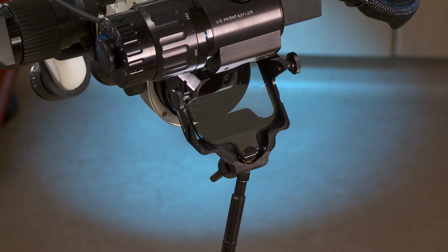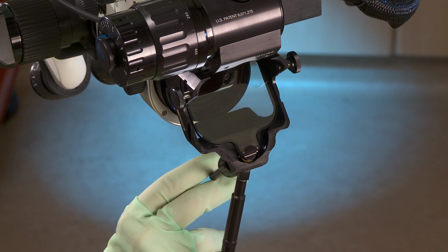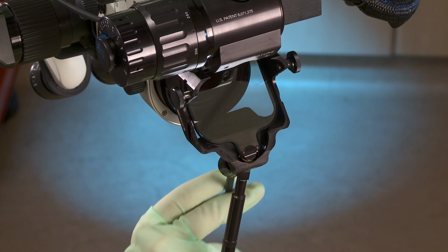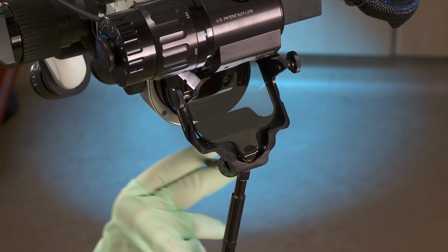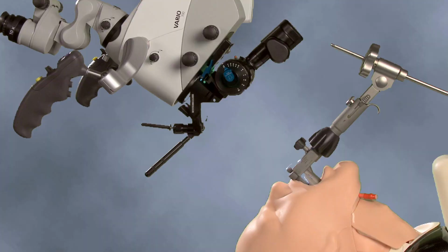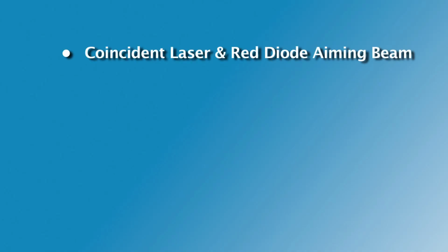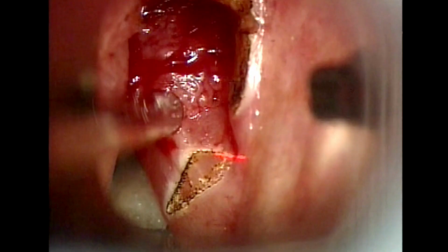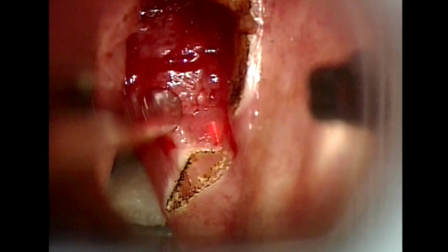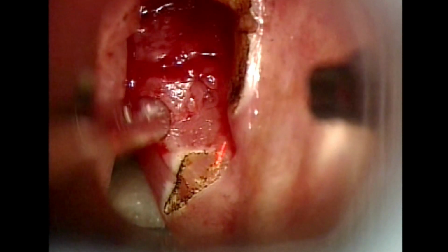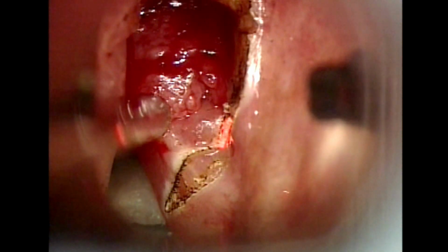Other than the size of the aperture, which is the opening for the laser beam to exit, and the gimbaled mirror, the functions and features of the three micromanipulators are nearly identical. When the micromanipulator is fully functioning, this is what the surgeon should expect. The CO2 laser beam and red diode laser aiming beam are coincident. This means the invisible treatment beam strikes the tissue at the exact location where the aiming beam is seen.